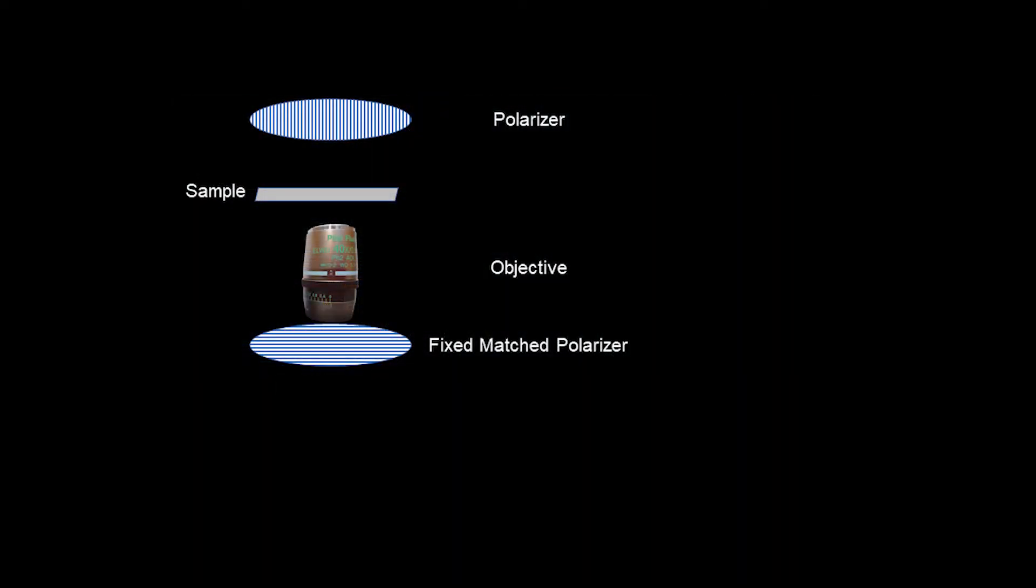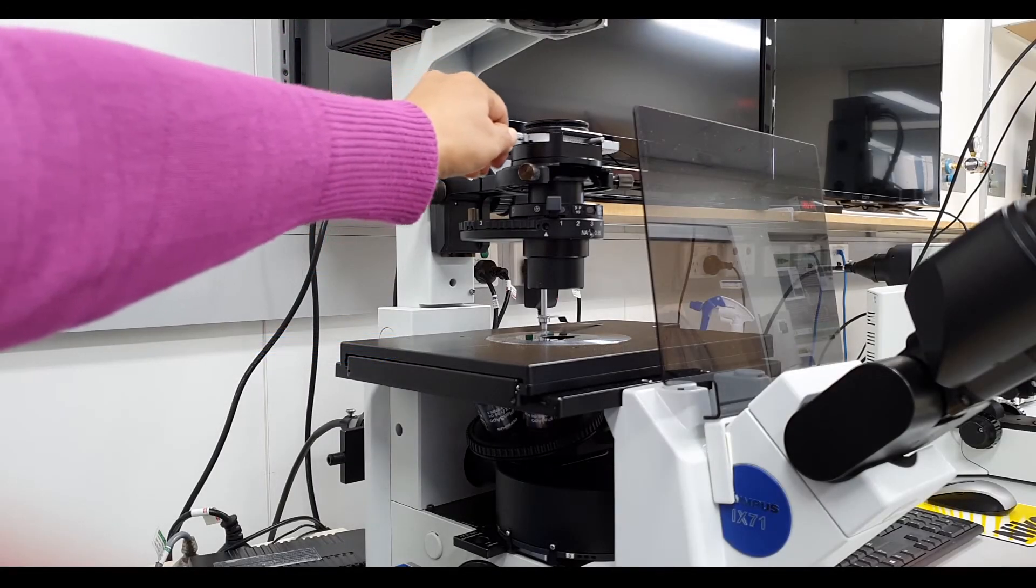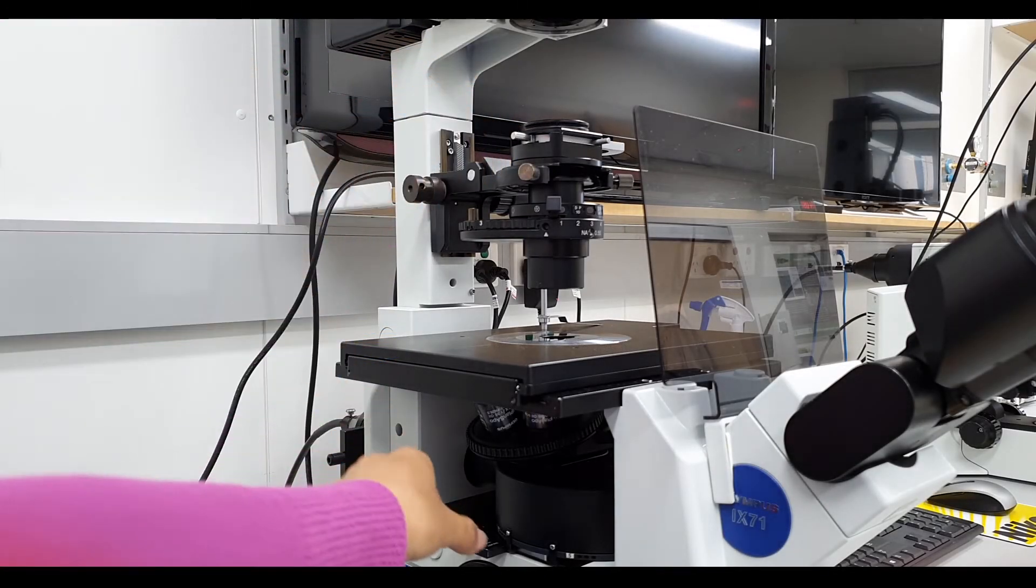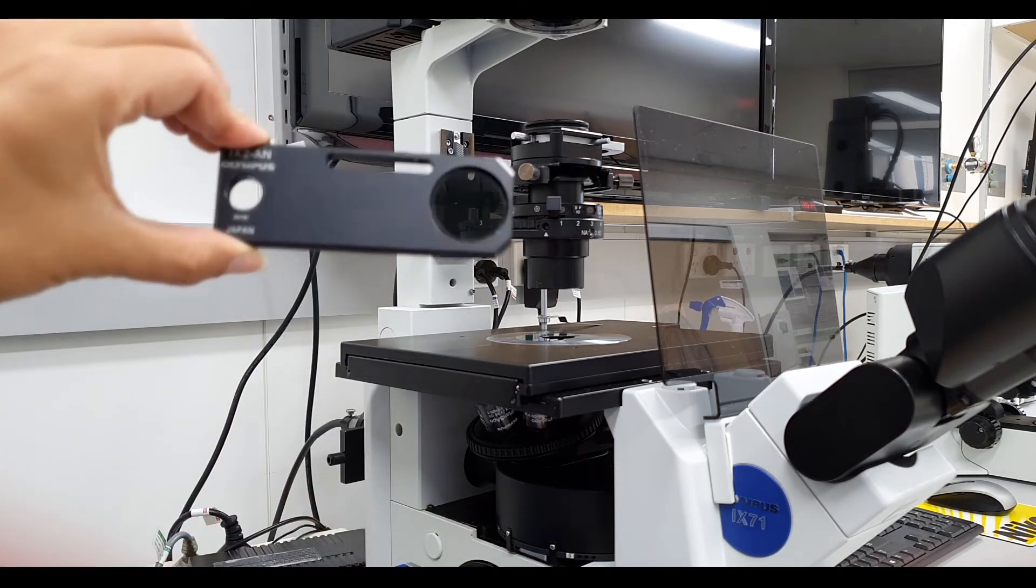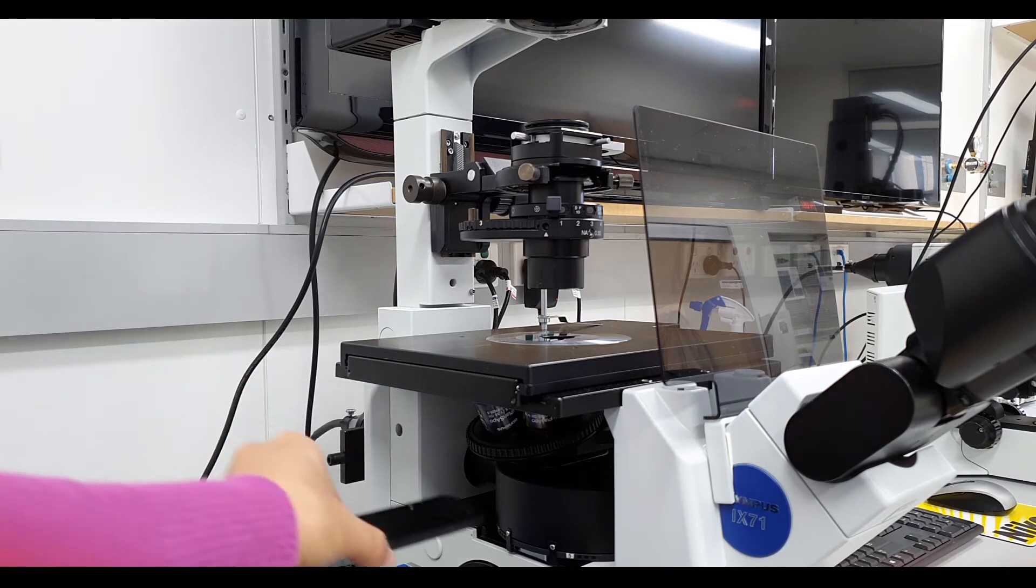The light from the lamp goes through a polarizer and then after the light has transmitted through the sample and objective, it goes through a fixed matching cross polarizer before the light goes to the detector.